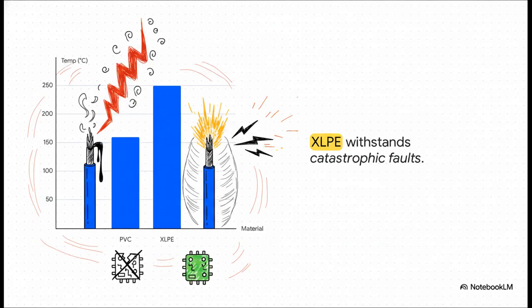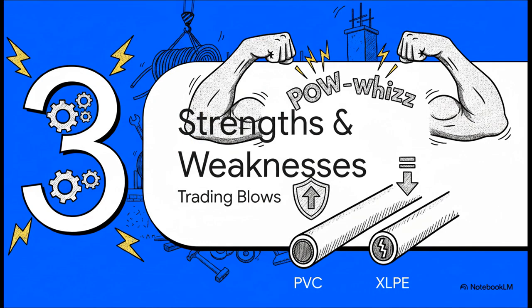And this brilliantly illustrates the extreme stakes during a catastrophic fault. If a short circuit happens, you get an immense spike of heat generated in just a fraction of a second. For a maximum of 5 seconds, PVC can withstand 160 degrees Celsius before it starts deforming. But XLPE can survive a staggering 250 degrees. So in a major fault event, the PVC might melt, causing a permanent, very expensive failure, while the XLPE survives to operate another day. Let's move on to Section 3, Strengths and Weaknesses, Trading Blows.